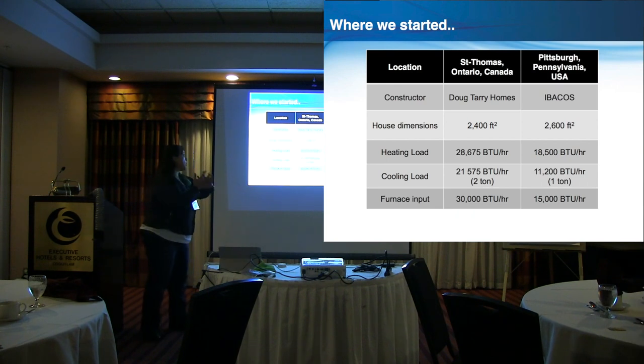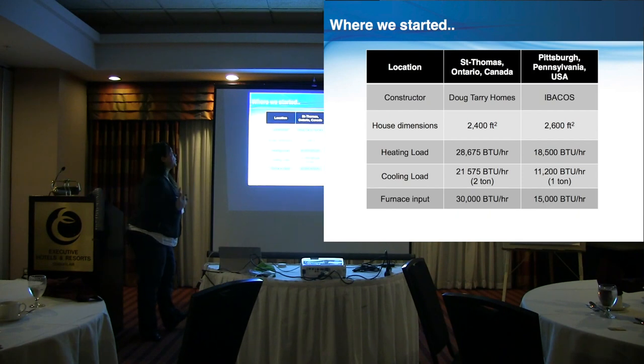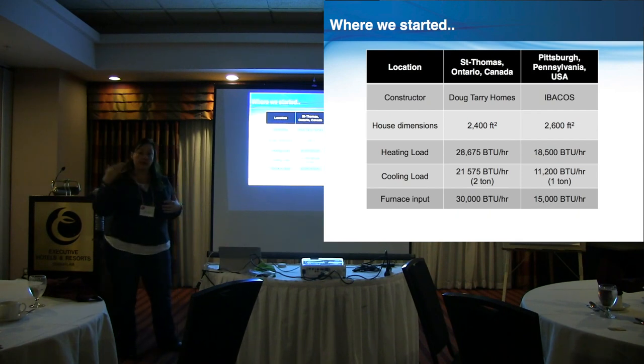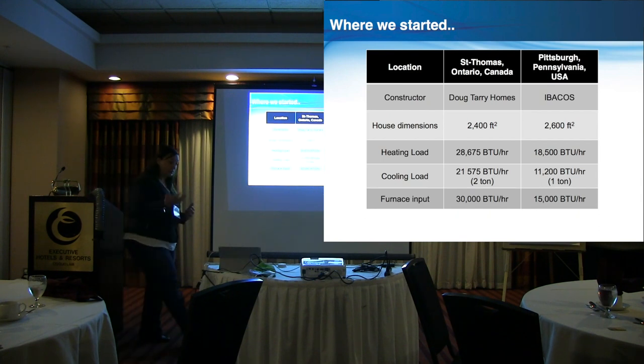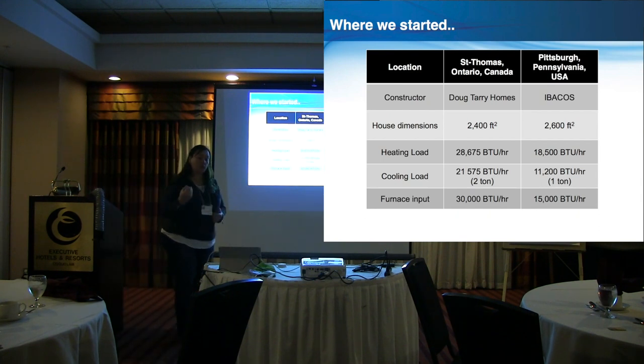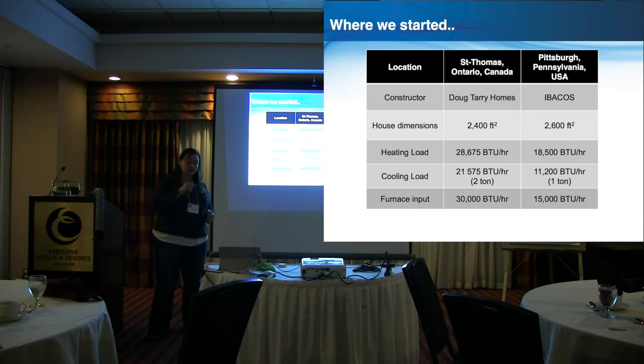So Doug Terry Homes in southwestern Ontario, 2,400 square feet, high performance house. It's Energy Star Next Generation, and this was a couple of years ago. So 28,000 BTU furnace, or 28,000 load, we put in a 30,000 BTU furnace. The cooling load, just over 21,000, so we put in a 2-ton.